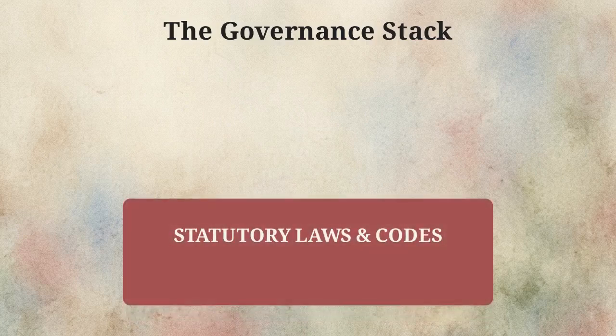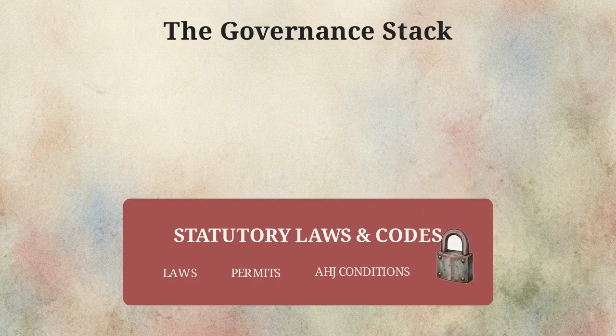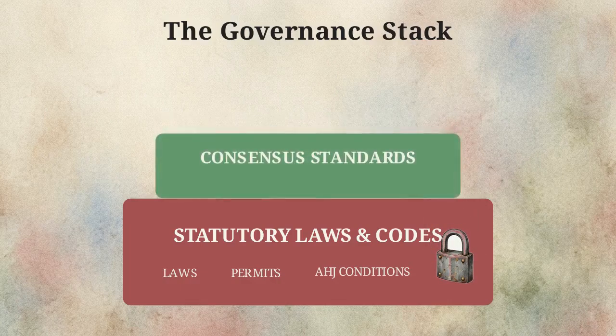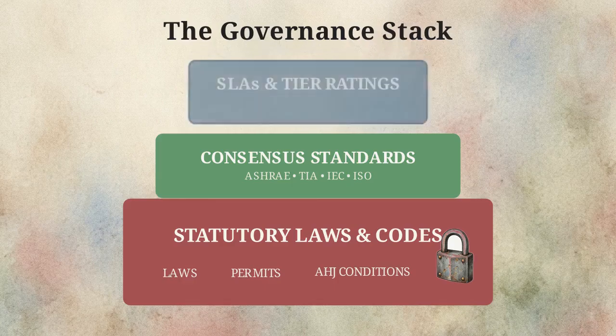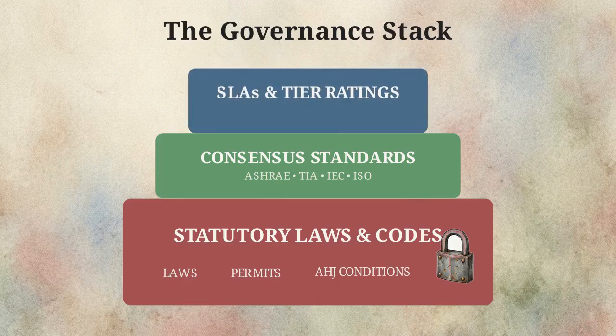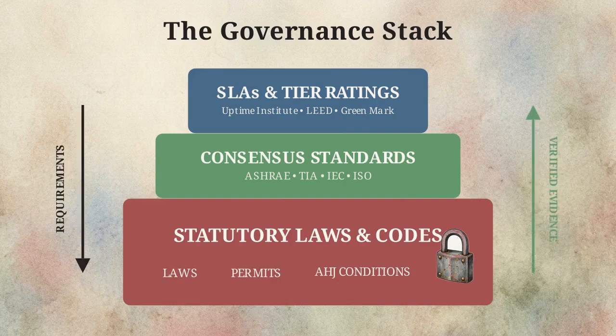Looking at this diagram of the governance stack, the absolute foundation is the bottom red tier. These are adopted statutory laws, local building permits, and authority having jurisdiction, or AHJ, conditions. They are mandatory and strictly non-waivable. Directly above that legal baseline, we find the middle layer of consensus guidelines and sector standards, like ASHRAE. At the very top sit the owner-specific service level agreements and independent tier rating objectives. A voluntary standard, a sustainability rating, or an owner waiver can never legally displace an adopted AHJ safety condition.